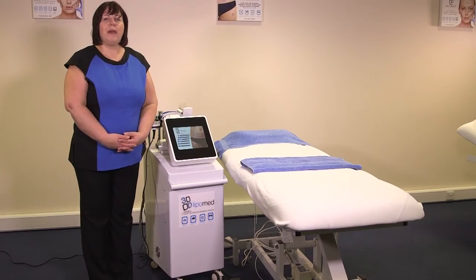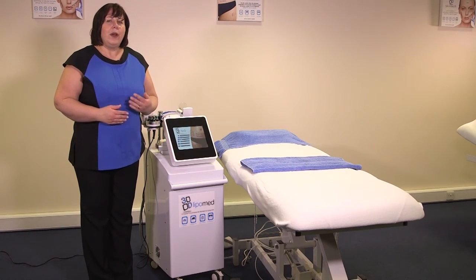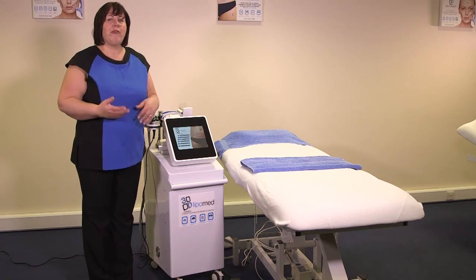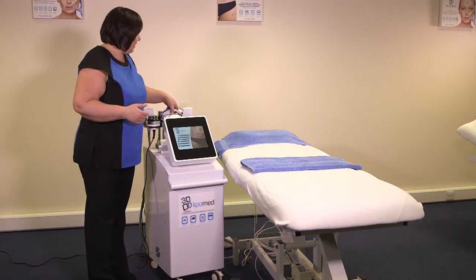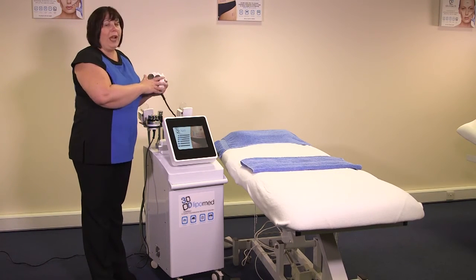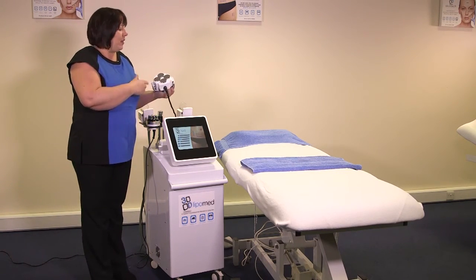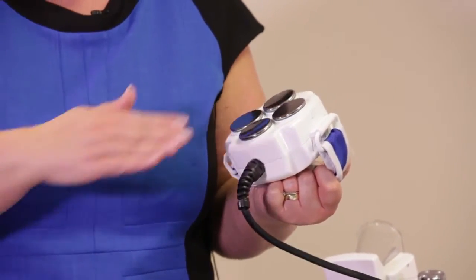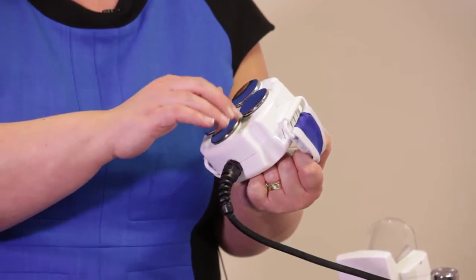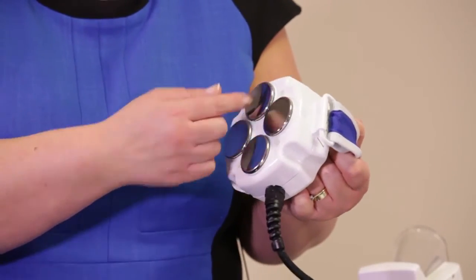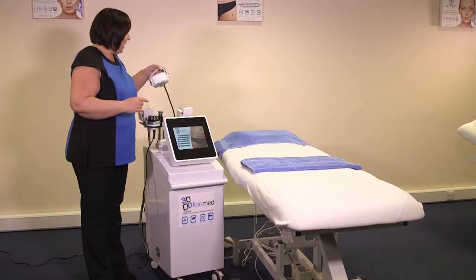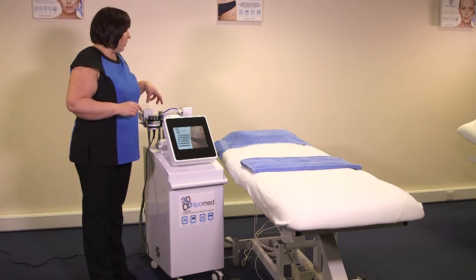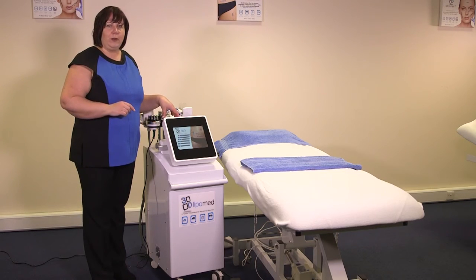So now we're going to go through some maintenance of the 3D lipo. When you're finished using your heads, what we must ensure is that the gel is removed from the head straight away. So once you finish your cavitation, take some bedroll, wipe away the excess of the gel. Then you must use the sanitizer provided onto cotton pads or onto the tissue and wipe over, and it sanitizes the whole area, making sure you get in between the transducers as well. Same with the 6 pixel radio frequency head and the 4 pixel. Each one should be sanitized after each individual use.